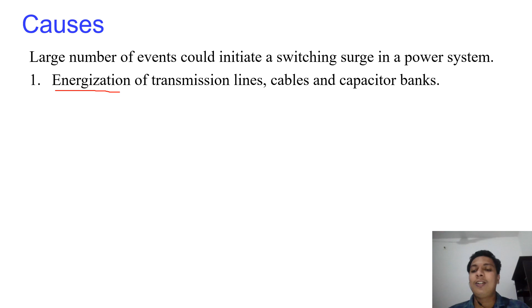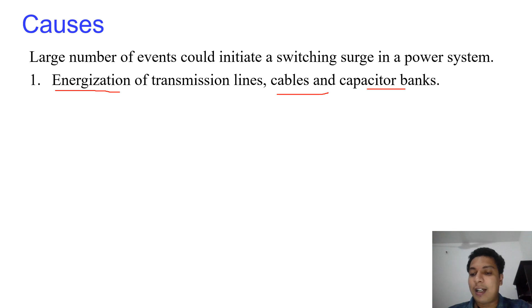A large number of events can initiate this, so we will discuss them one after another. One is energization of the transmission line, as I said, like switching on the supply. So energization of the transmission line, or it can be a cable, or a capacitor bank. Whenever we are energizing or adding something new to the network, it can cause a transient because there is a switching operation involved.